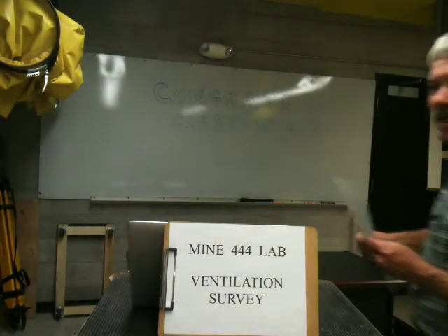That's a difference of 4.4%, and that's actually pretty good considering that some of our measurements took place outside with no boundaries to contain the airflow. But then again, we would expect the numbers to be fairly close since the air exhausted by the fans does equal the air coming in through the glass doors, but also there is probably leakage being pulled in from the labs. So I think that's a pretty good number. Again, a fairly basic demonstration, but we hope this illustrates the principle behind a ventilation survey.